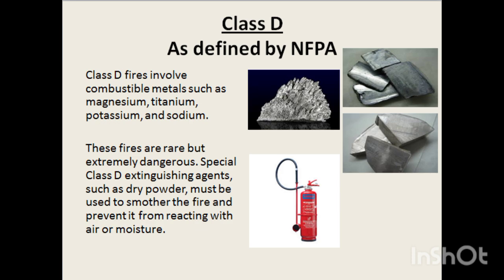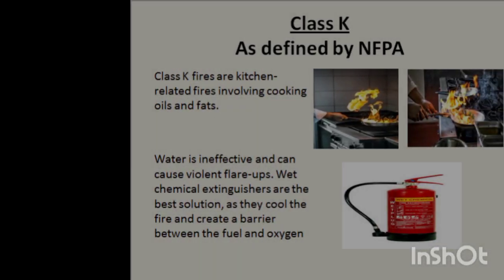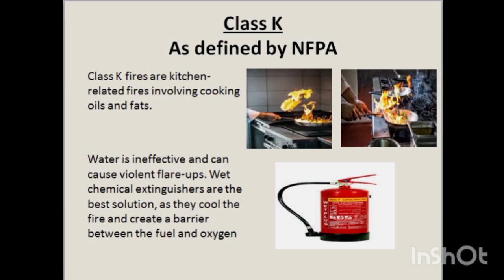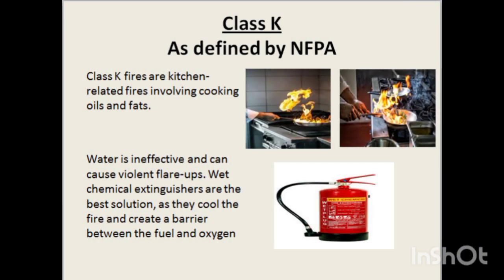Finally, Class K fires are kitchen-related fires involving cooking oils and fats. Water is ineffective and can cause violent flare-ups. Wet chemical extinguishers are the best solution, as they cool the fire and create a barrier between the fuel and oxygen.